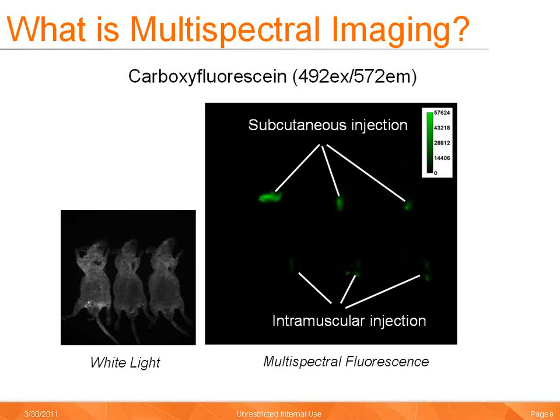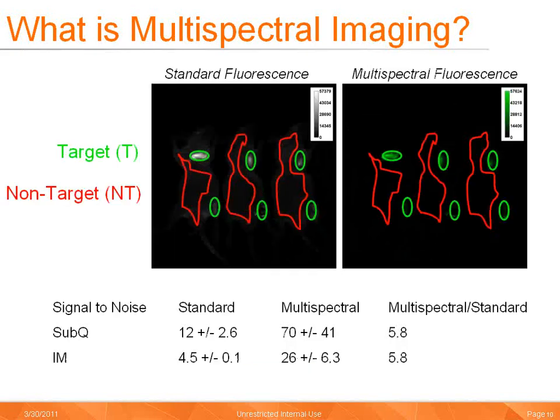Here we will use imaging of a green fluorophore to illustrate the first utility of multispectral imaging. Carboxyfluorescein, which has a peak excitation of 492 and emission of 572, was administered both subcutaneously and intramuscularly. The image to the left is a white light image showing the layout of the sample, and the image to the right is the multispectral fluorescent image. The sample was imaged using standard single-filter excitation and single-filter emission imaging, and intensity analysis was performed for both target and non-target regions reported as a ratio. Comparing signal-to-noise ratios, we achieved an almost 6x gain in signal-to-noise with multispectral imaging, which translates into improved overall sensitivity.